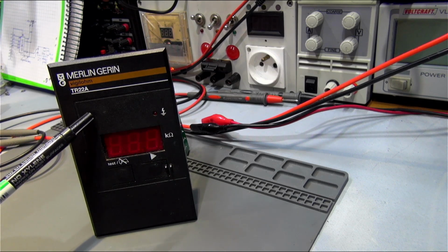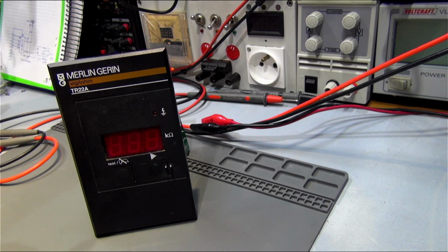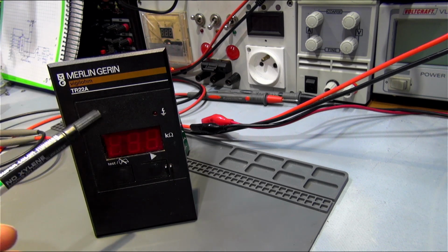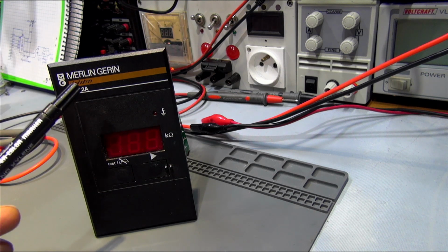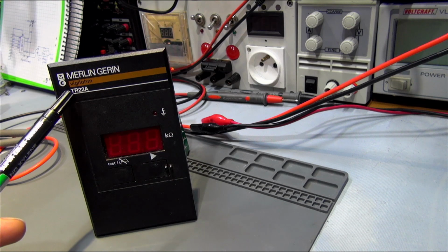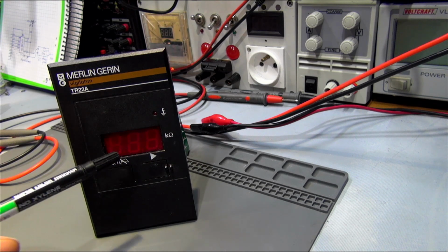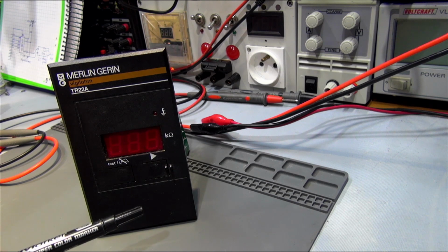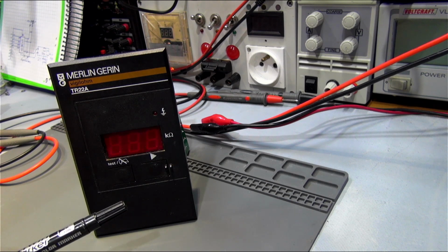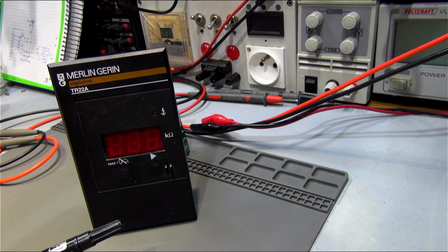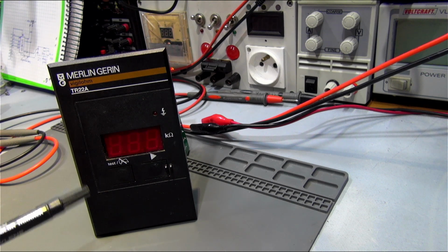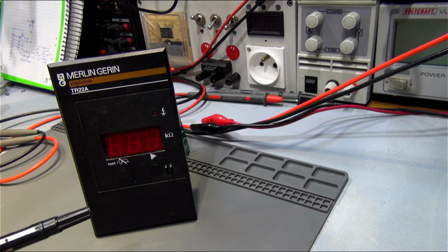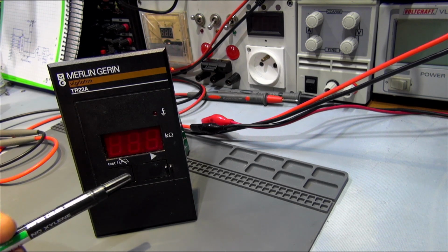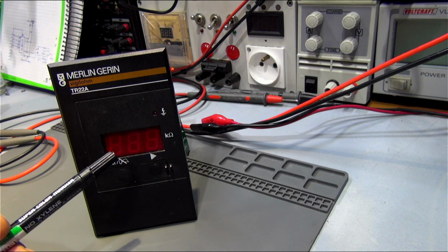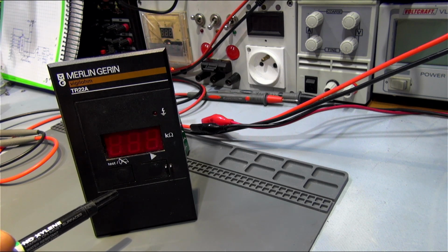Today I have this device on the bench, which is a permanent isolation monitor, and this one is broken actually. It doesn't work. This is the TR22A version, and the purpose of this thing is to measure leak current between earth and neutral, or earth and grounding, depending on the neutral or earth point treatment you need in your industrial installation.